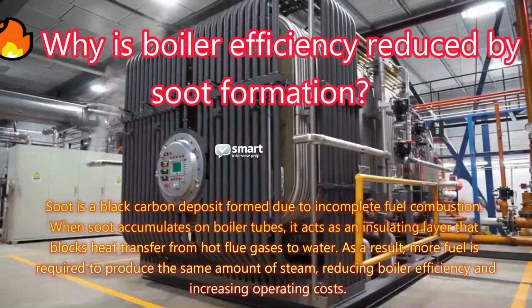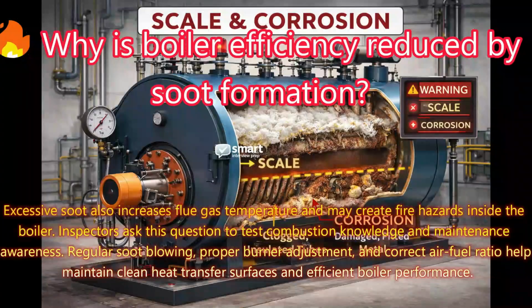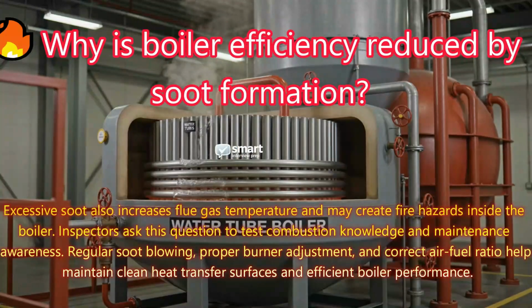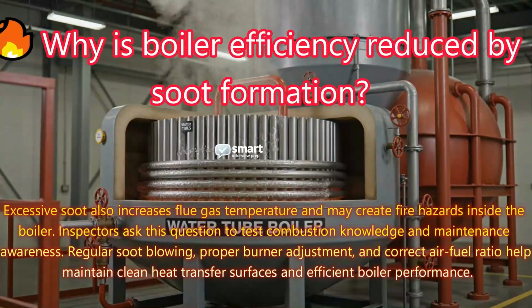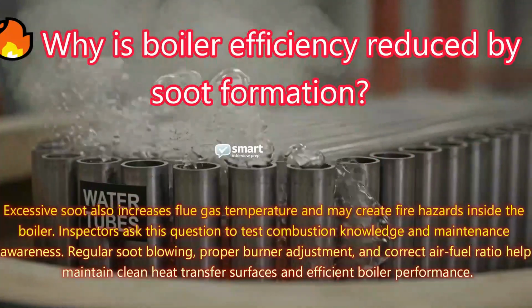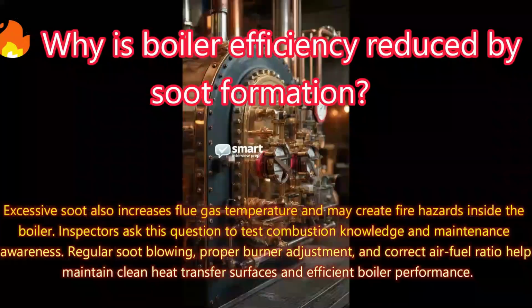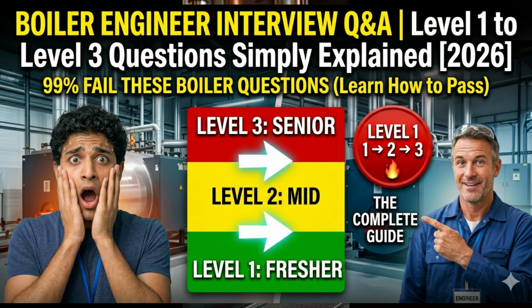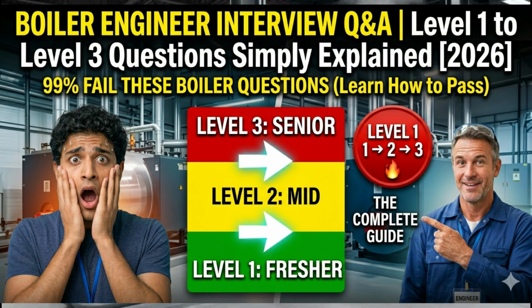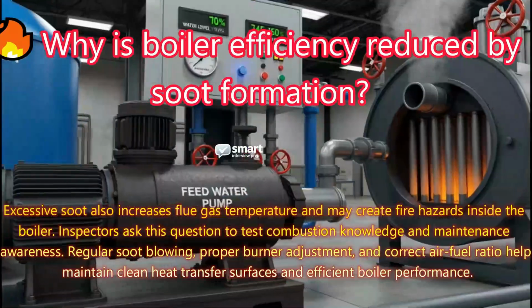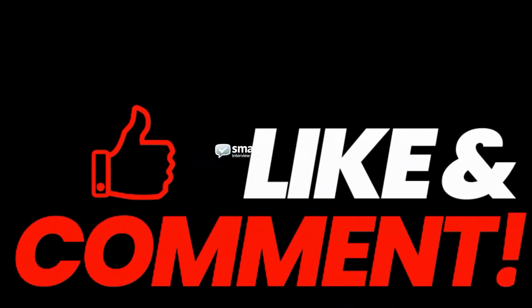increasing operating costs. Excessive soot also increases flue gas temperature and may create fire hazards inside the boiler. Inspectors ask this question to test combustion knowledge and maintenance awareness. Regular soot blowing, proper burner adjustment, and correct air-fuel ratio help maintain clean heat transfer surfaces and efficient boiler performance.